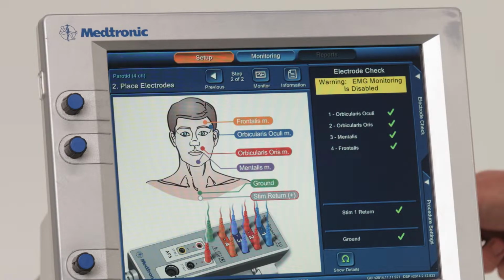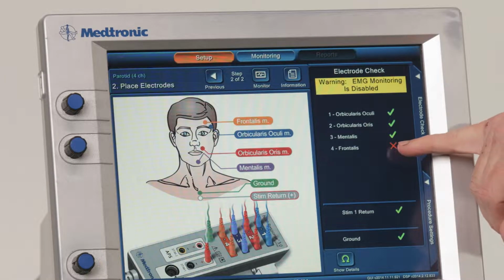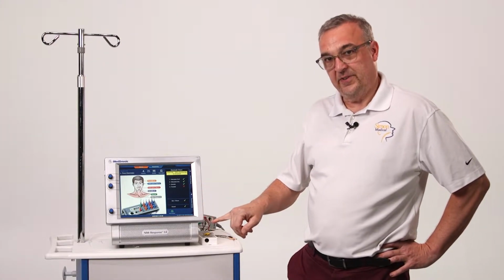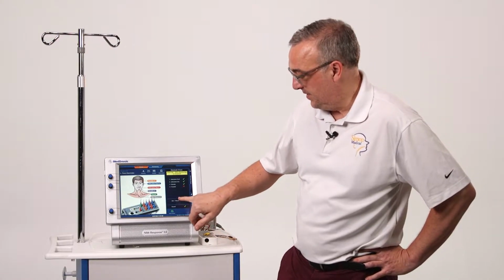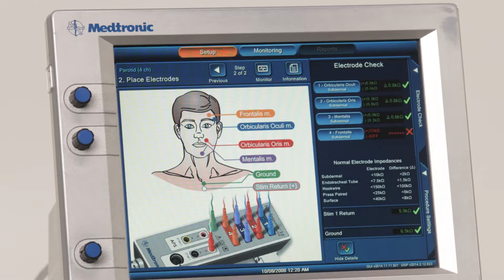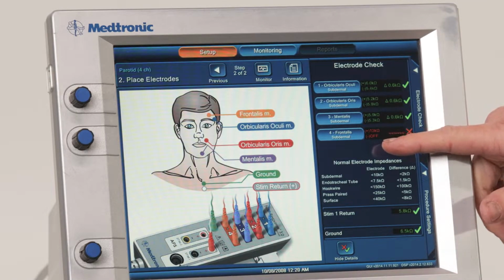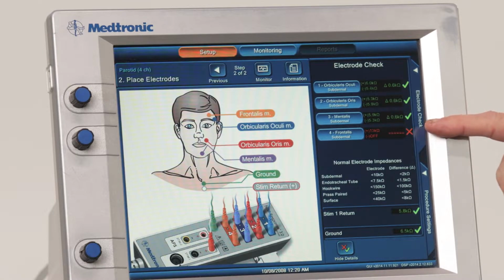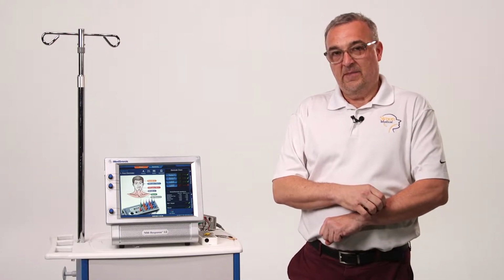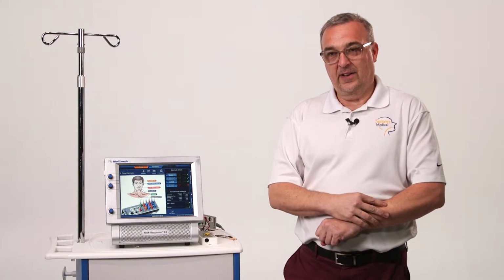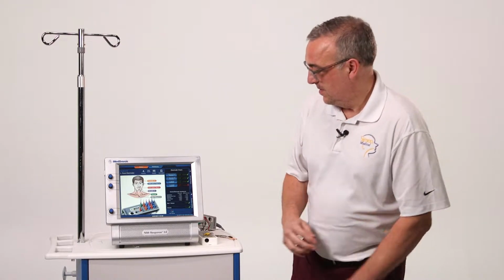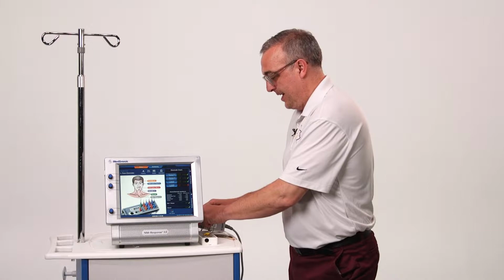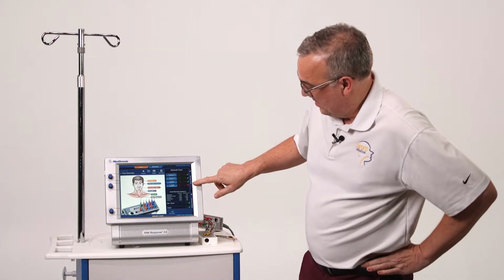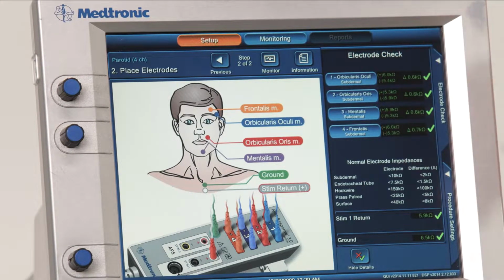So if I remove one of the electrodes, the frontalis, we've got an X here. So we know we have very high impedance here, which means either the electrode's not on or something else is wrong, or it's loose, it's not making full contact. We can touch down here for details, and we can see we don't even have a number here. So basically it's off. So you know that electrode has come off. If you've got a number here that's high and it's still red, that probably just means the electrode may have slipped out, it's just touching the skin, it may be under the surgical tape, but you need to check that electrode, okay? Fortunately, my patient is right here, and I can plug it back in, and we should see that go back to positive, so we're good.